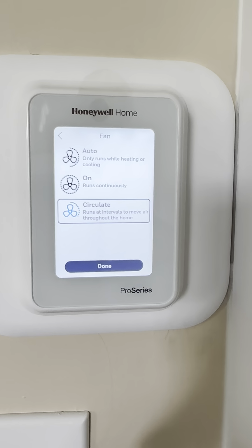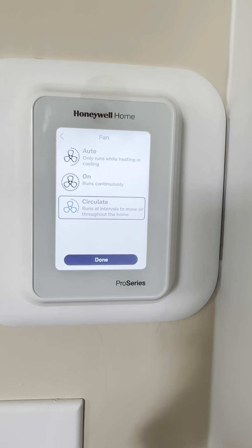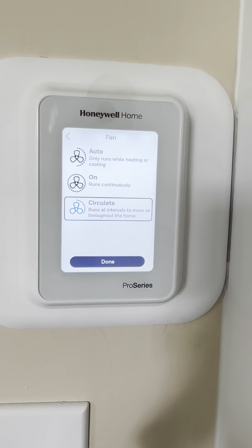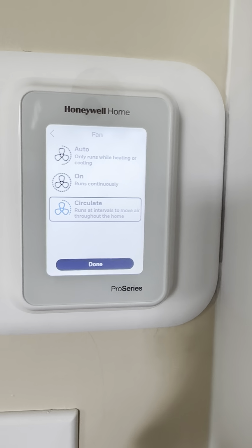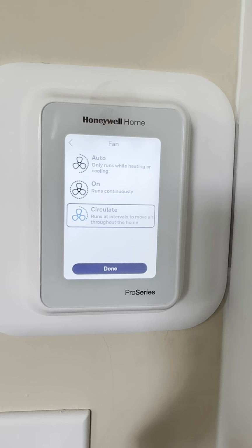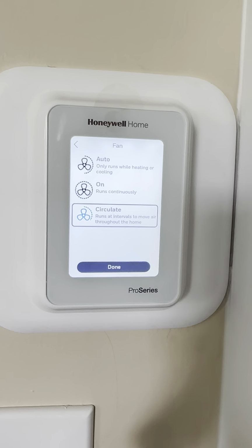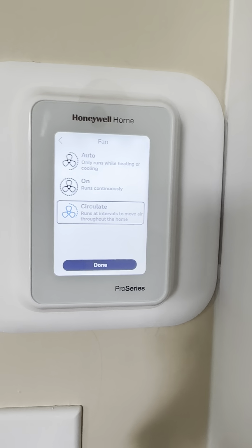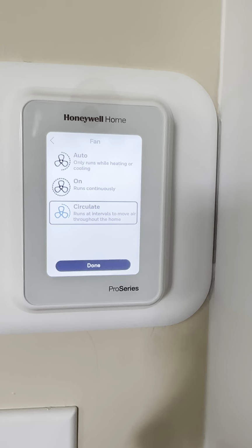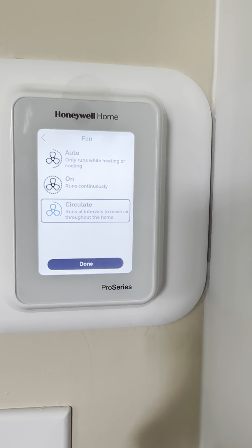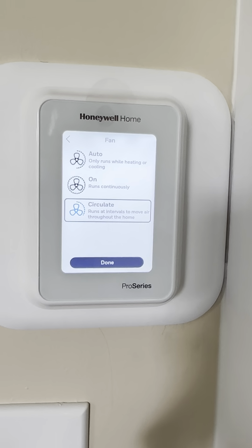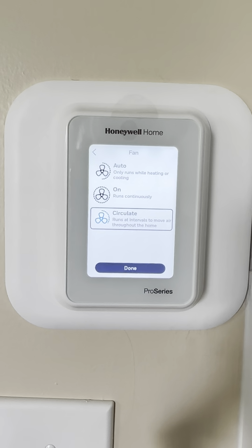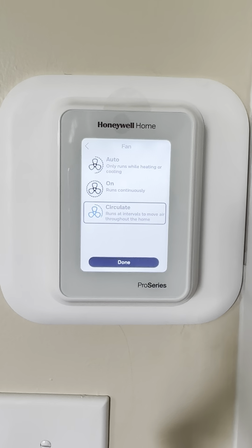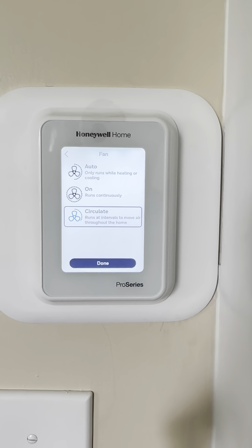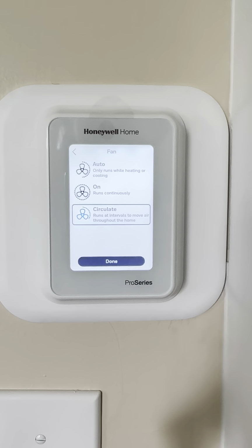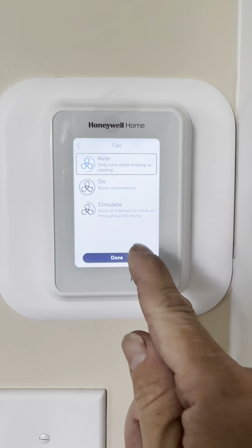Now, the circulate mode is nice for two-story houses or very long houses that have many rooms. So that's going to run the fan at periodic intervals throughout the day that help to mix the air through the house. So if you have a two-story house and your ductwork is set up properly, it will help to even out the temperatures from upstairs to downstairs. So very helpful option there. It will still run when it's supposed to, but it's gonna add a few extra runtime intervals throughout the day. So we're gonna go back to auto for now.